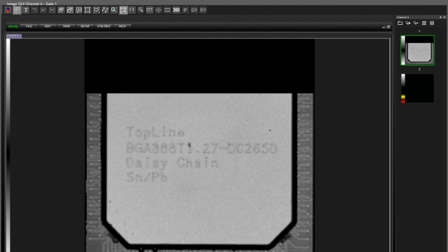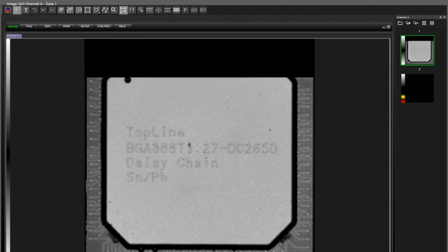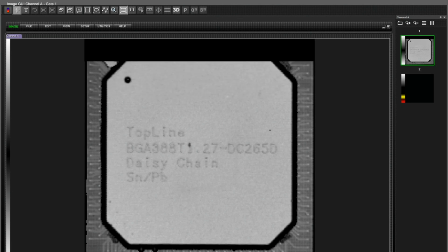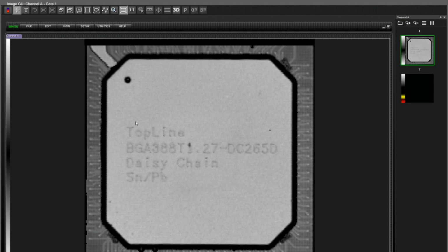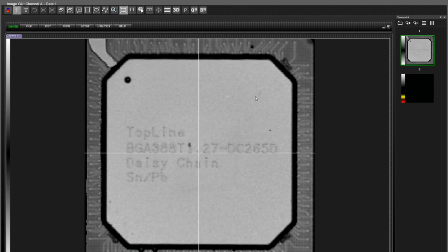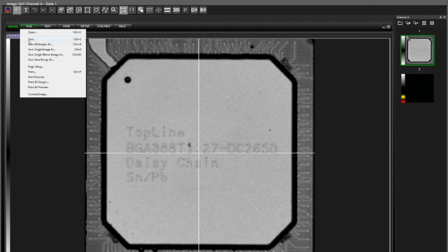From this image, even though it's not an internal scan, we can get a lot of information from it, such as the moulding mark. We have the laser marking and any imperfections that might be on the top surface we can see and record as well. So let's go ahead and save that. File, several save options. The first one will be saving in the Sonoscan format, which is image and parameters. The subsequent options are saving in bitmap, JPEG, PNG type format.